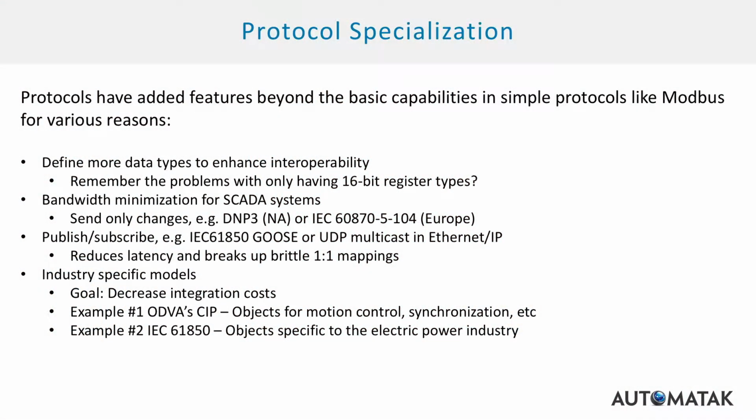And then finally, the last area where I'd say that protocols have really specialized over 5 or 6 decades of digitized control system protocols is developing industry-specific models. So instead of just having registers, like register 0 is a voltage, 2 is a current, 3 is a frequency, and having to understand that, they've developed industry-specific models where the protocol messages actually have structure that describes the process.